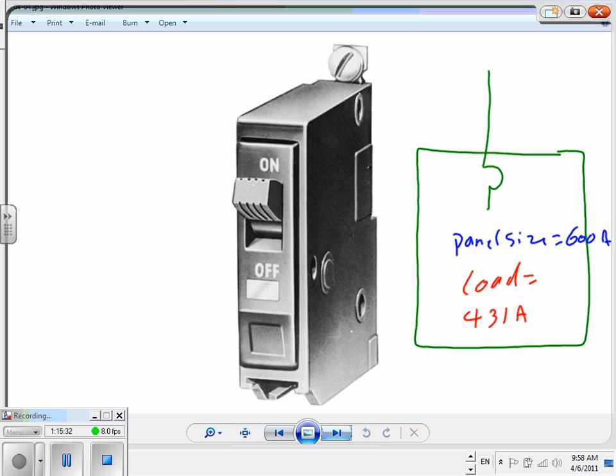Can you guys see that one? 310.12, 600. Now my overcurrent protection device, 310.13, based on the load of 431, which already took into consideration future expansion and all this good stuff. If you go to that one, I would have 450. So my overcurrent protection device would be 450 amp. And what do you think the conductor is going to be? It matches the overcurrent protection device, 450. So I can have a 600 amp panel fed from a 450 amp circuit breaker, and the cable has to match the overcurrent protection device.